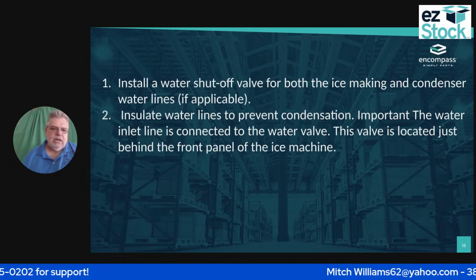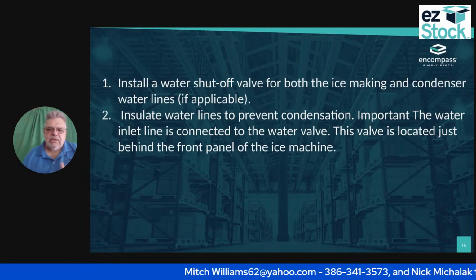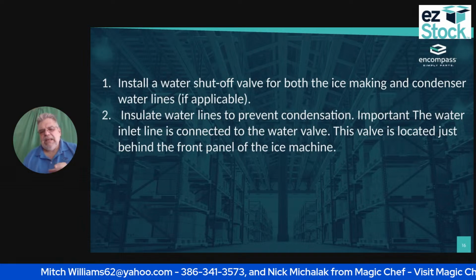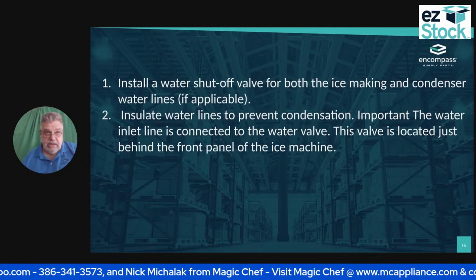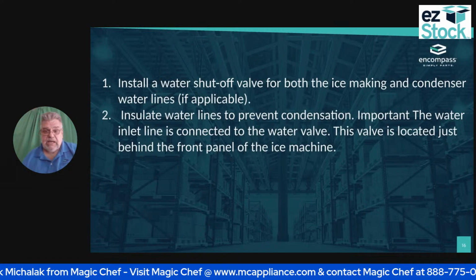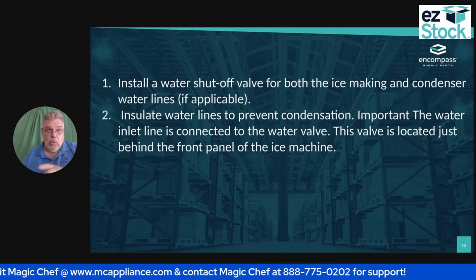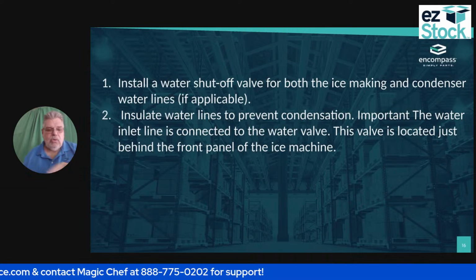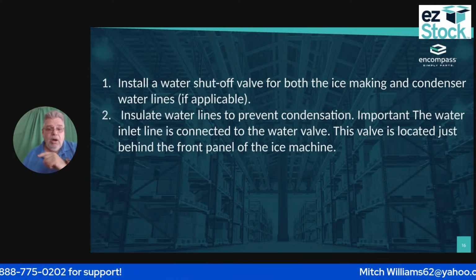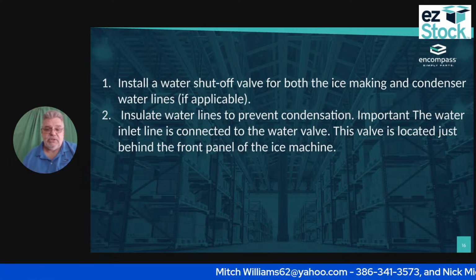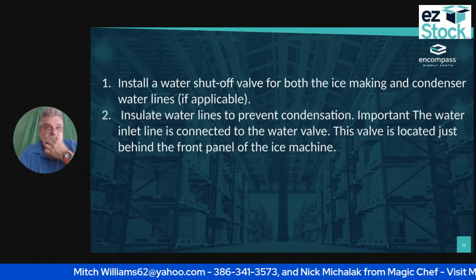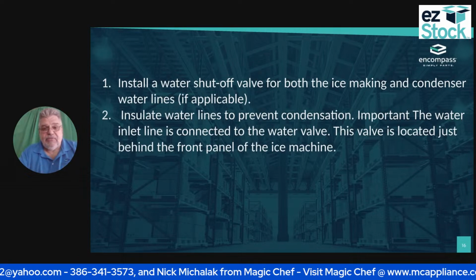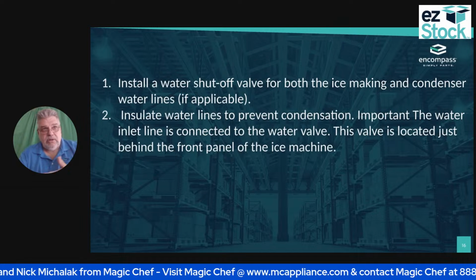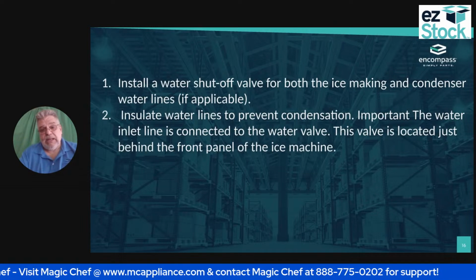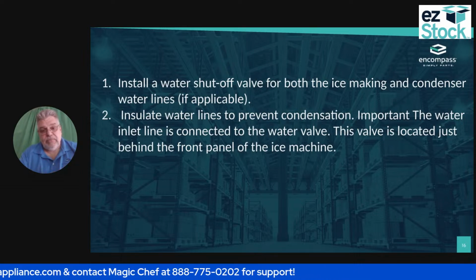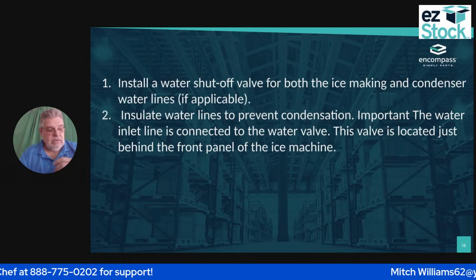Important, the water inlet connected to the water valve. This valve is located just behind the front panel of the ice machine. I need to make sure that I have it insulated, especially if I am up north and it gets kind of chilly. If I'm way down south, what will happen is I will get condensation off the water line, and it will look like I have a leak somewhere. So whenever I go in, that's the first thing that I look at, if I got any water coming off of the water line itself. And if so, I need to insulate that.